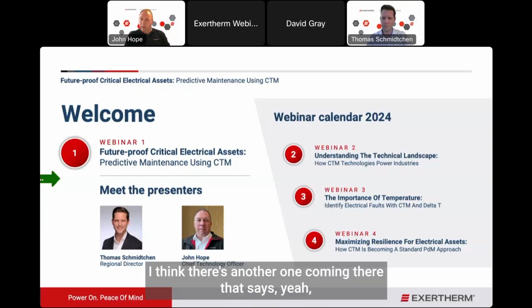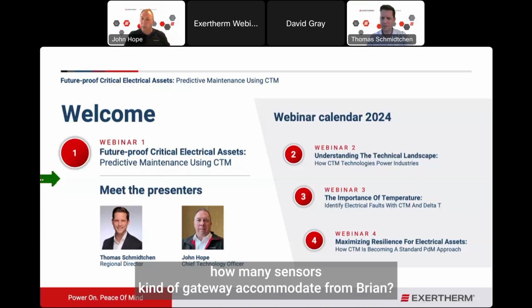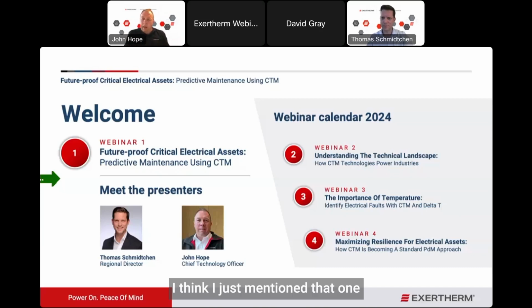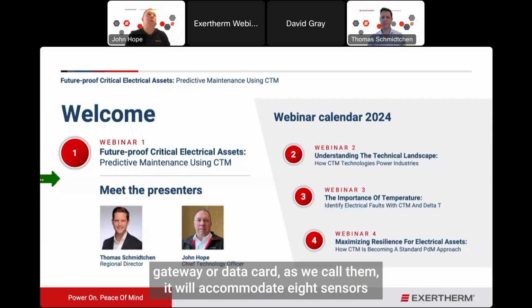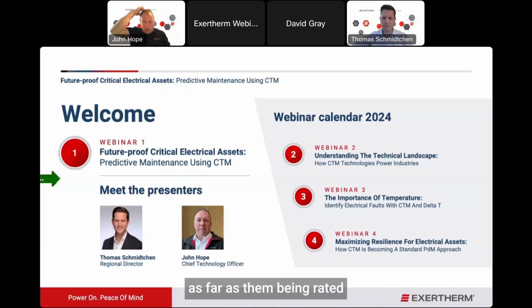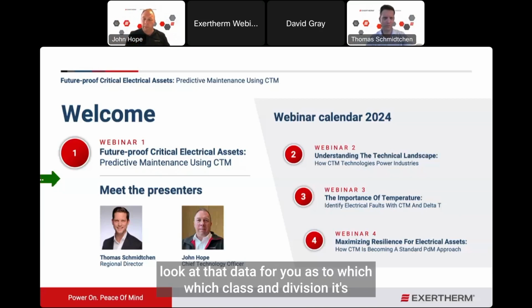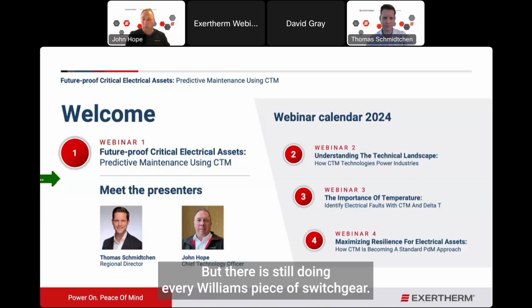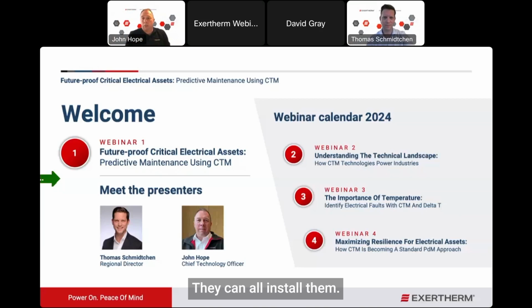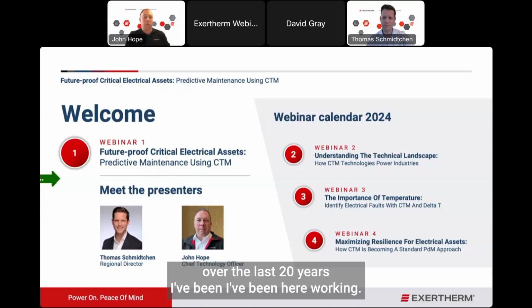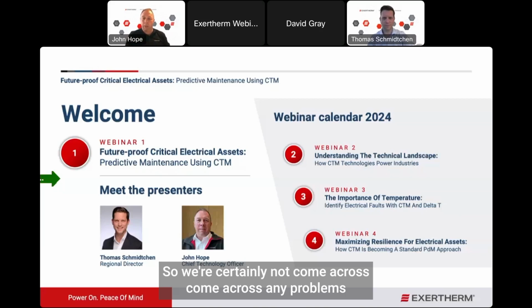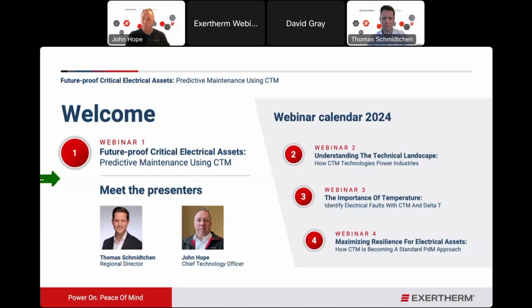I think there's another one coming there that says, how many sensors can a gateway accommodate, from Brian? I think I just mentioned that one gateway or data card, as we call them, will accommodate 8 sensors. As far as them being rated for Class 1 Division 2 areas, I'd have to go and check on that. We'll get that data for you as to which class and division it's suitable for. But they're installed in every OEM's piece of switchgear. We work with all the OEMs globally. They can all install them. There's not been an issue actually putting these sensors in that switchgear over the last 20 years that I've been here working. So we've certainly not come across any problems.